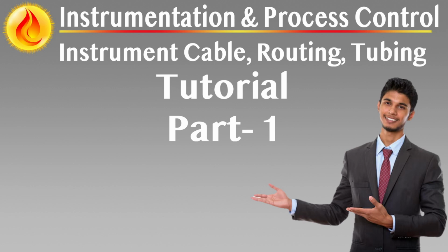In auxiliary rooms and control panels, system cables should be logically routed to pre-designated boards or termination blocks. Connectors must be rated for vibration tolerance, contact resistance, and pin alignment integrity. Test certification and vendor compliance are mandatory. Spares must be incorporated at a rate of at least 10 to 20% to allow for system expansion or field modifications without retrofitting core cabling infrastructure.